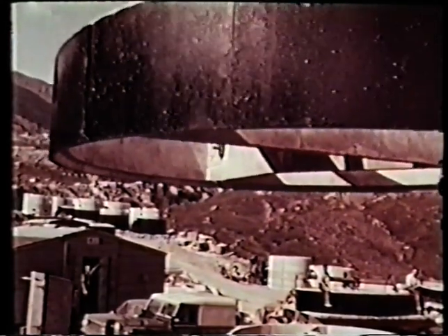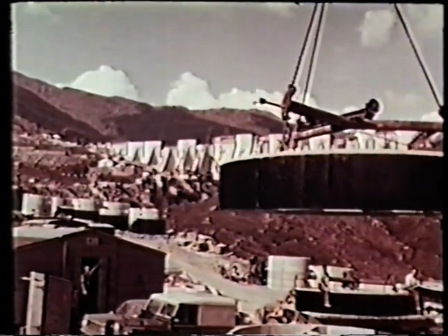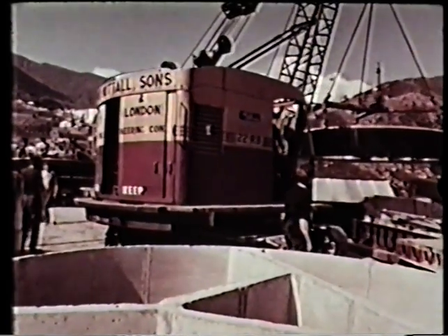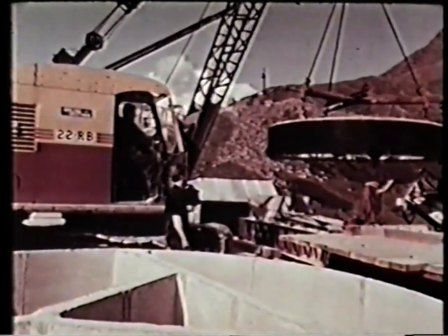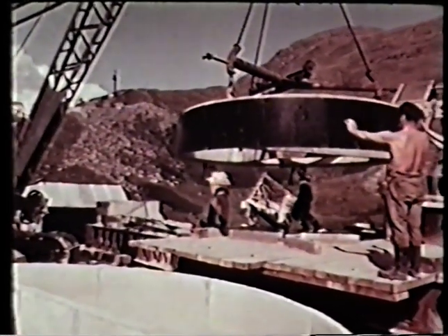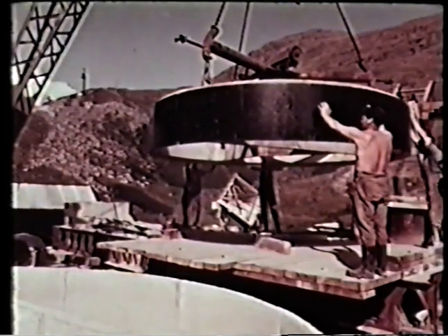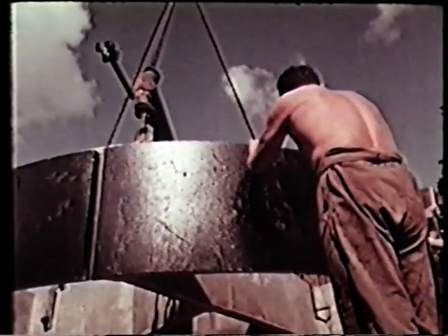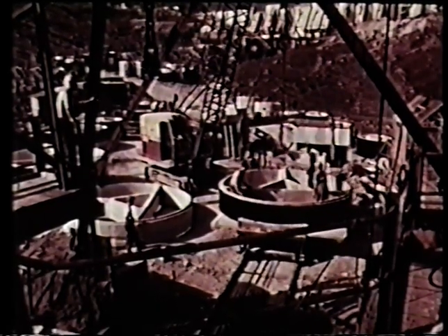Some 350 yards from the foot of the dam and situated above the transformer hall area emerges a 1,200-foot shaft which combines the functions of ventilation and main cable duct. This shaft is lined with precast concrete rings 13 foot internal diameter. These rings are partitioned and provide two ducts for the two cable circuits and to lead air down to the ventilation plant in the cavern, and a third to contain an access stairway.